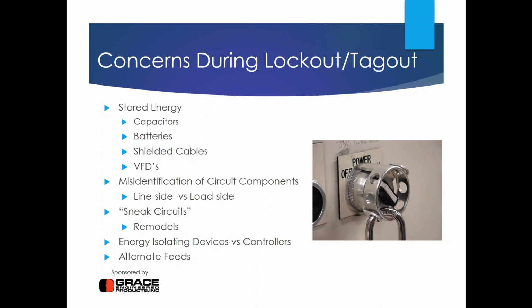The idea of energy isolating devices versus controllers is also very important. In the picture you see on the right, you see a selector switch that is lockable, and the key part of that is a selector switch is not an energy isolating device. It is a controlling device, and it would not be legal to lock that out with a lockout lock. If you were going to lock it out, use something other than a lockout lock. The appropriate energy isolating device would actually be the circuit breaker that feeds that entire panel. Locking out this particular controller, there might be 2 or 3 other possible ways for that device to become energized. So you cannot lock out, tag out controlling devices, push buttons, toggle switches, selector switches, emergency stop circuits, etc. You will not be legal to lock those out. You're going to lock out only energy isolating devices, also known as source devices.